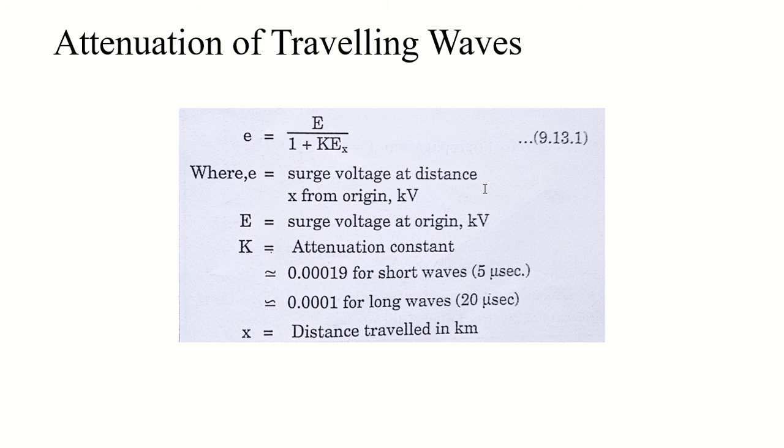Now wave attenuation because of corona is more pronounced for positive waves compared to negative waves. That is also something we discussed earlier. And why was that happening? It is because of greater corona loss for positive waves.